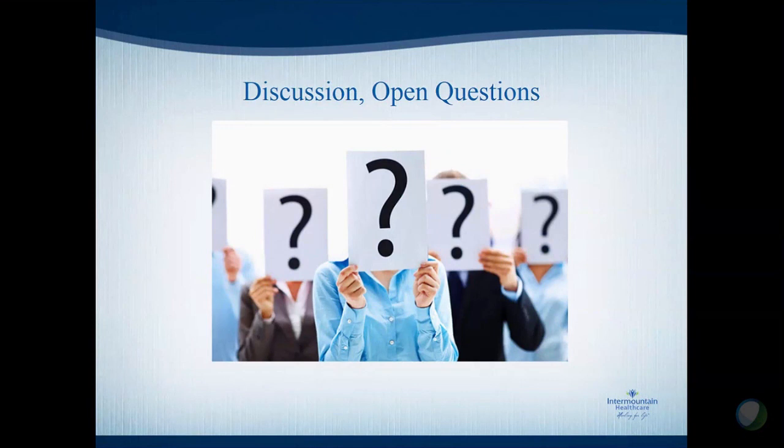Hey, Jim, Len here. Okay, I have a question. Let me shut the door because I'm getting feedback. The question is, you mentioned gauges, that the NFPA has interest in gauges. Do they have interest in measuring pressure properly and systematically at hyperbaric chambers, and getting rid of gauge pressure? You know where I'm going with this. We've had talks about this. You've had an abstract or something about this in the past, that the influence of altitude biases the pressure. We're not all talking the same thing. So does the NFPA have any interest in going there?